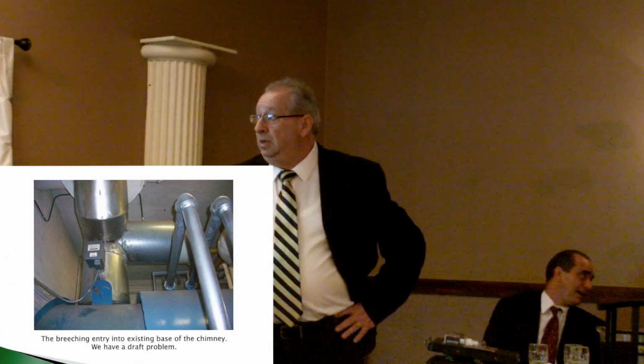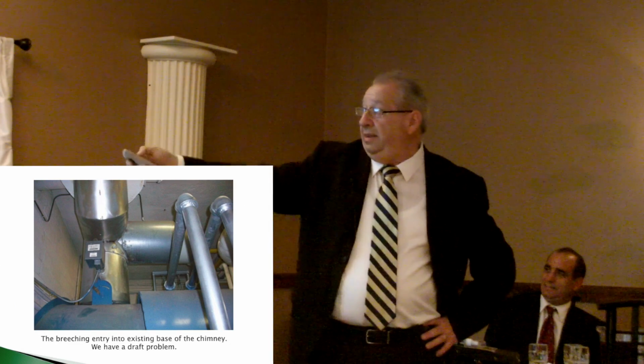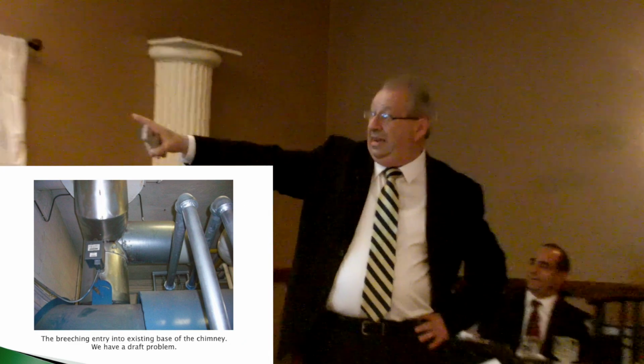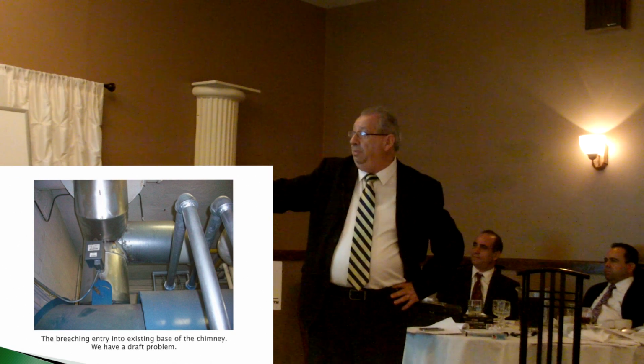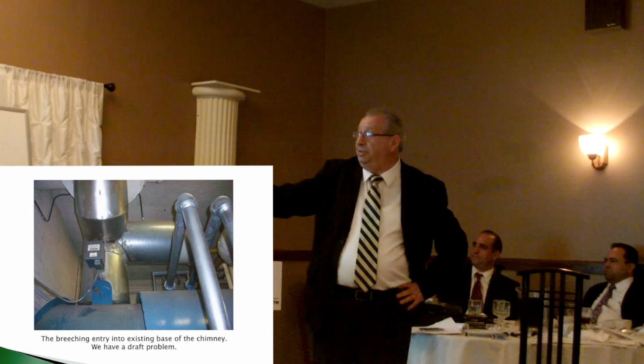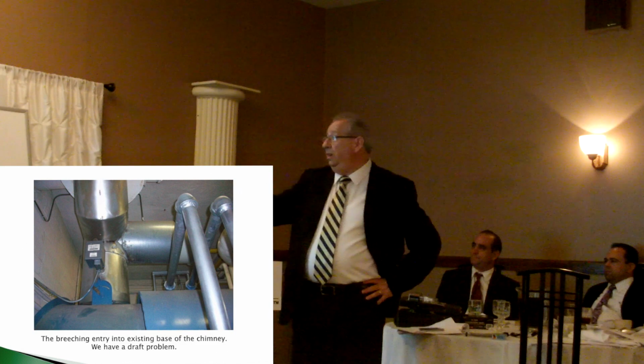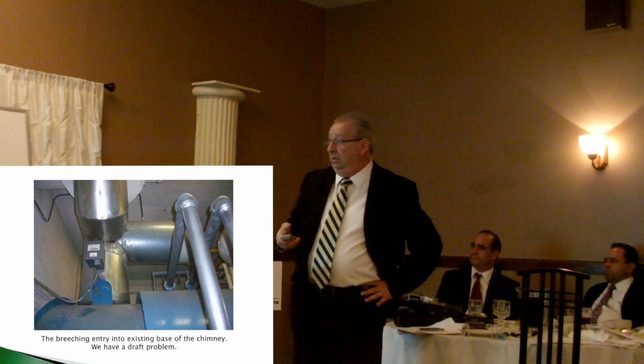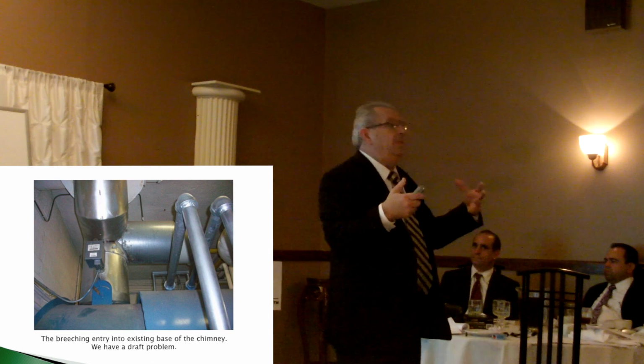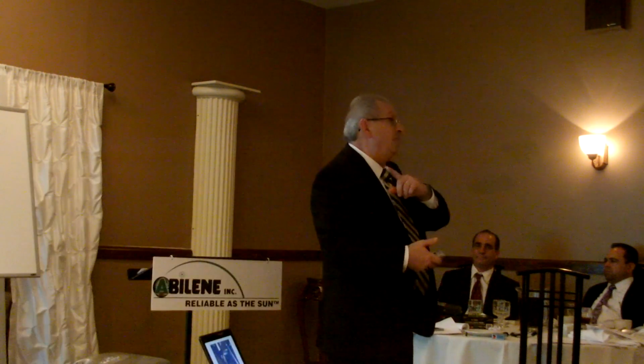Okay? So we have a barometric. Anybody see the barometric? Bingo, right there on the bottom. Okay, that's a barometric. The breeching actually goes up right there. That's where it enters into the chimney, into the base of the chimney. And then we didn't know where to put a smoke alarm, so we created this thing. I don't want to be a Monday quarterback, but this is a 9 years old job.